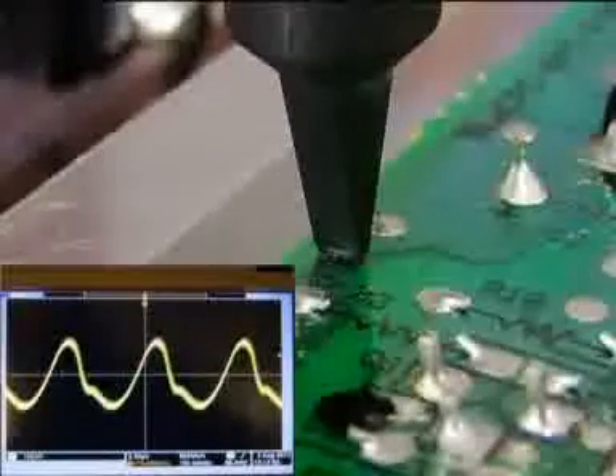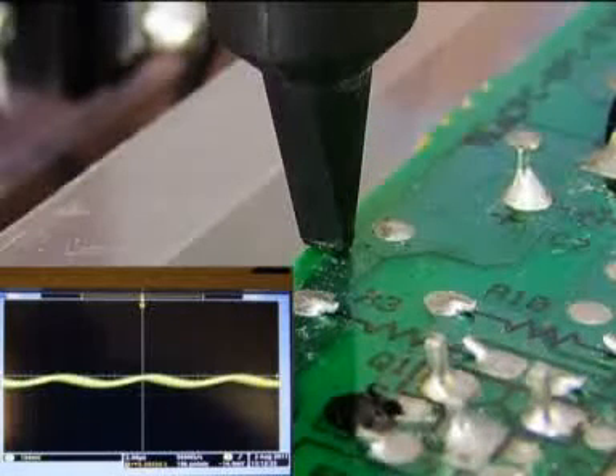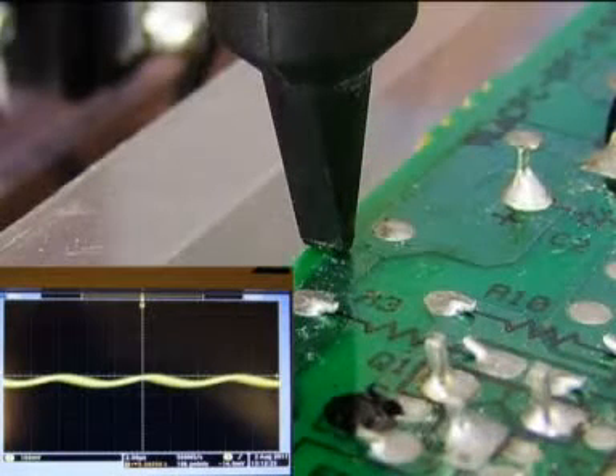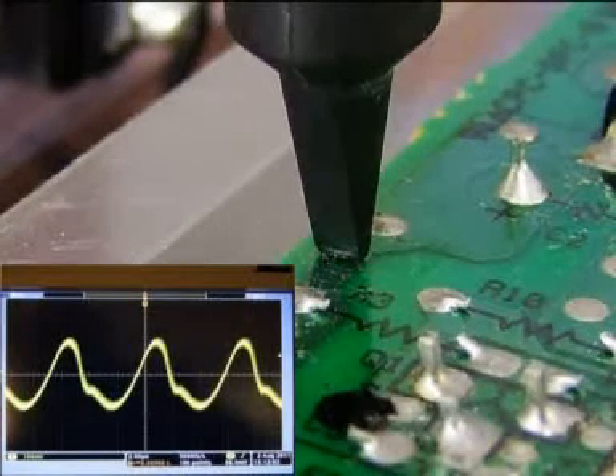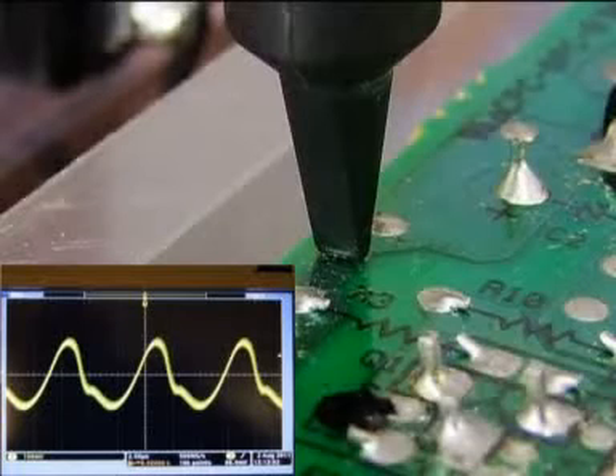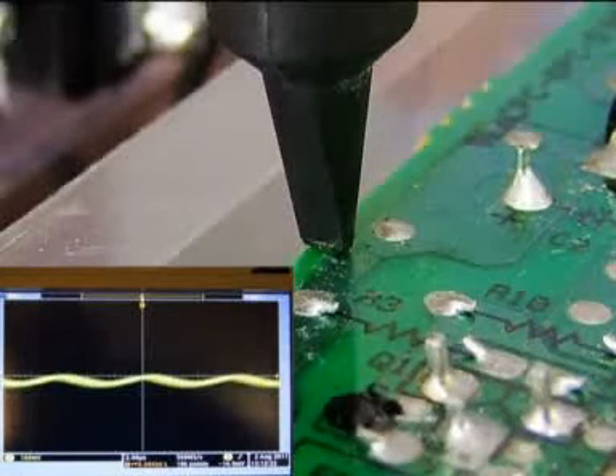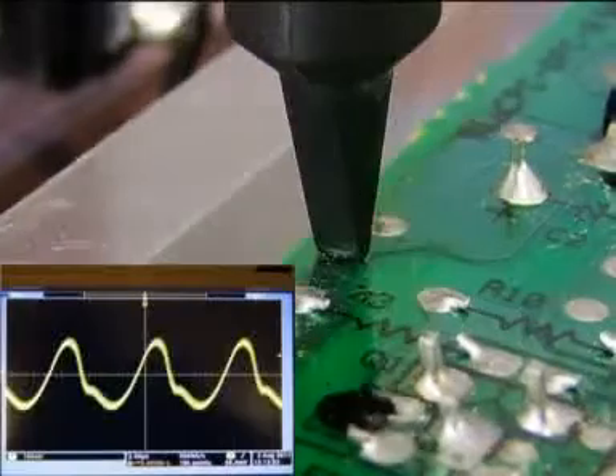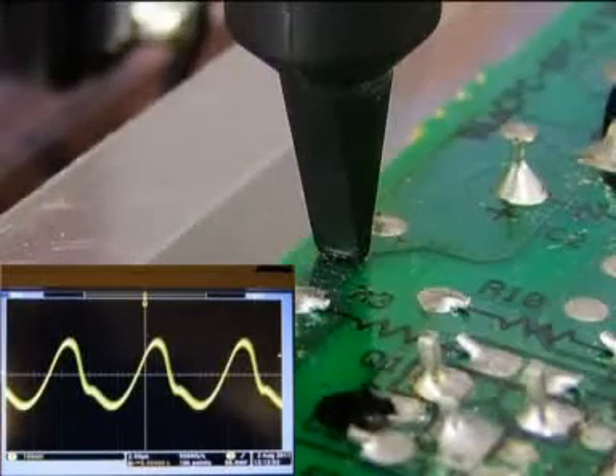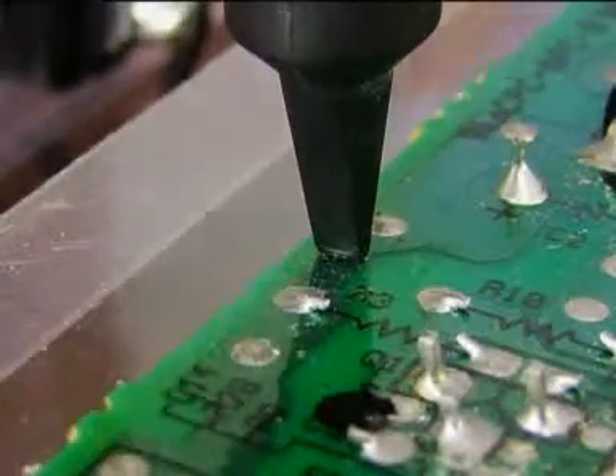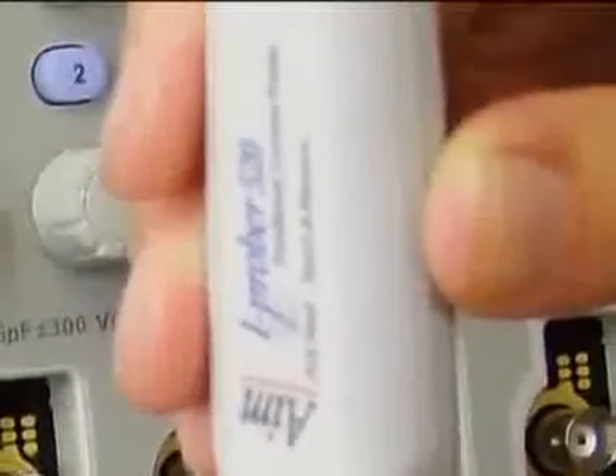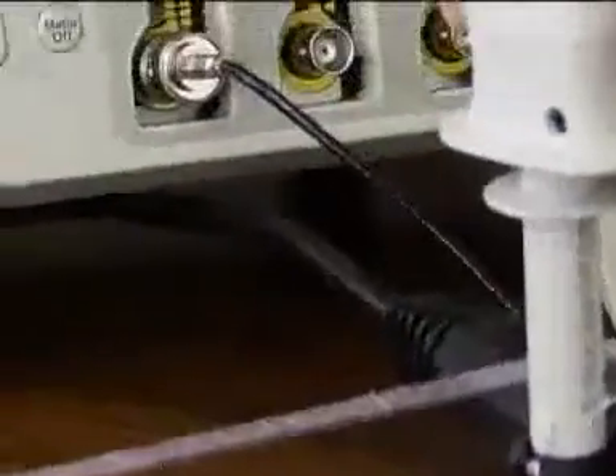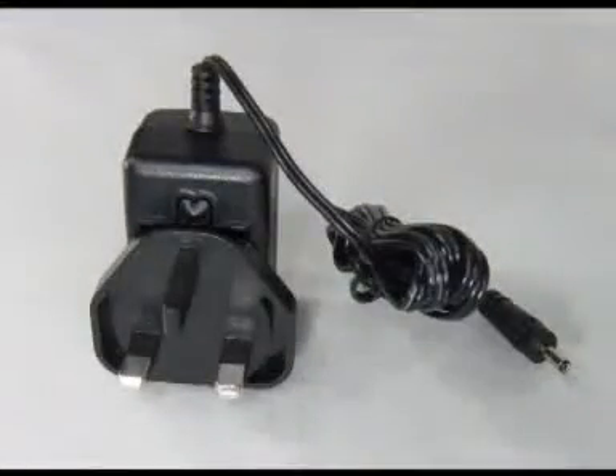By contrast, the iProber signal is critically affected by the position of the probe relative to the conductor. What the iProber is measuring is the magnetic field at a precisely defined point in space. We call the iProber a positional current probe because the measurement is critically dependent on the position. It consists of the probe, which is connected via 1.5 meters of cable to the base unit, which has a short BNC terminated cable for connection to an oscilloscope. Power is provided via a small power adapter that plugs into the base unit.